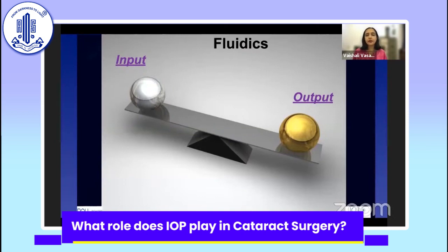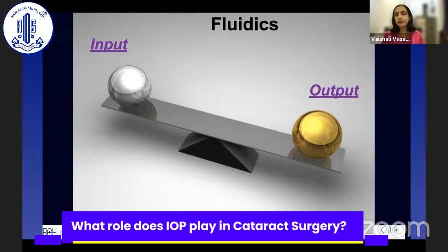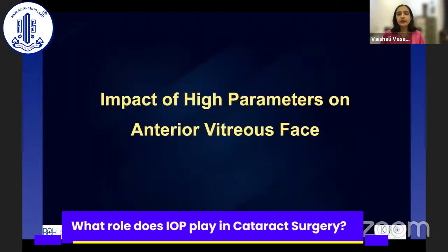The basic principle is that bottle height input and aspiration flow rate output must balance each other. If you have a high flow rate, you must compensate with a higher bottle height — which is what most of us do, leaving the pole at one fixed high level regardless of the surgical stage. The key message is that what we are doing causes intraocular pressure much higher than expected, while clinically we strive for only 15–18 mmHg. We must be conscious of this.